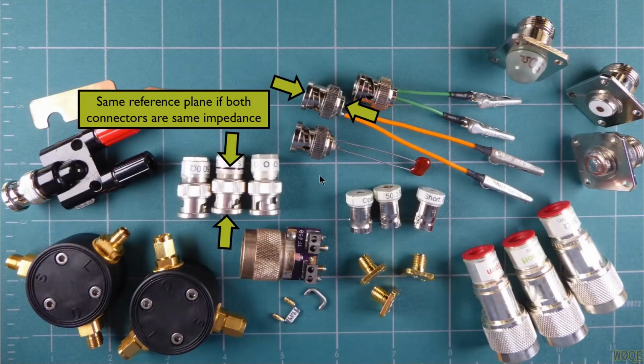What I typically use to connect to odd components is something which has some little clips on it a lot of times. And that obviously begs for some kind of line extension again. In this case, I have these particular BNC male adapters where the reference plane is marked with this black line, and that is the offset for this adapter. It turns out to be exactly the same offset as from here to here. These are the same kind of BNC connectors. These just happen to be silver plated, and they're compression type connectors, so I could take these apart and put the open short load in there easily.